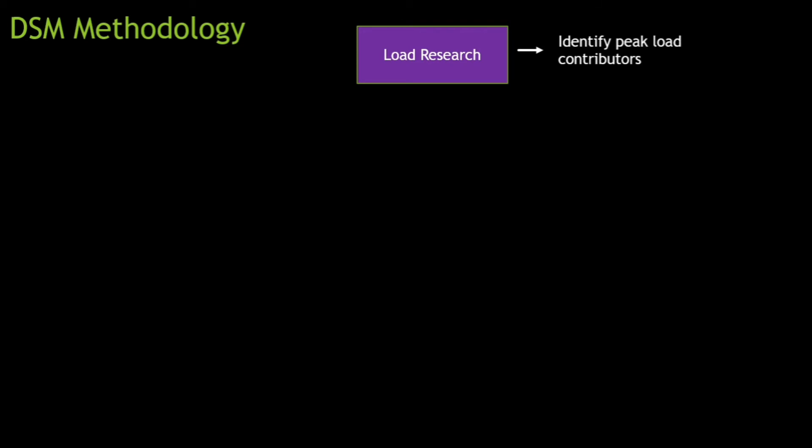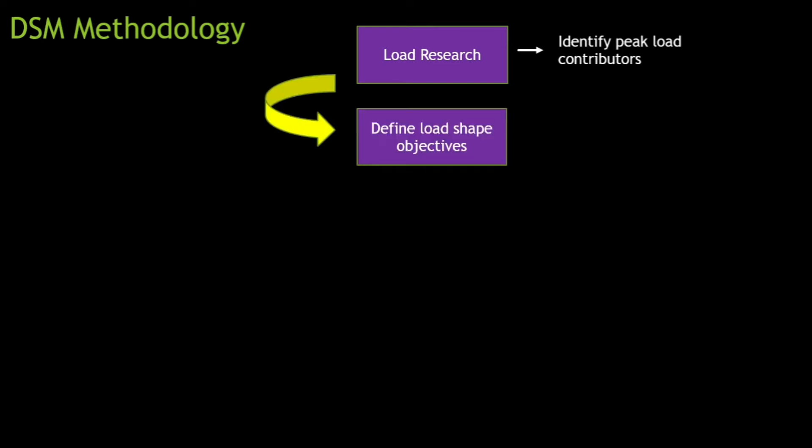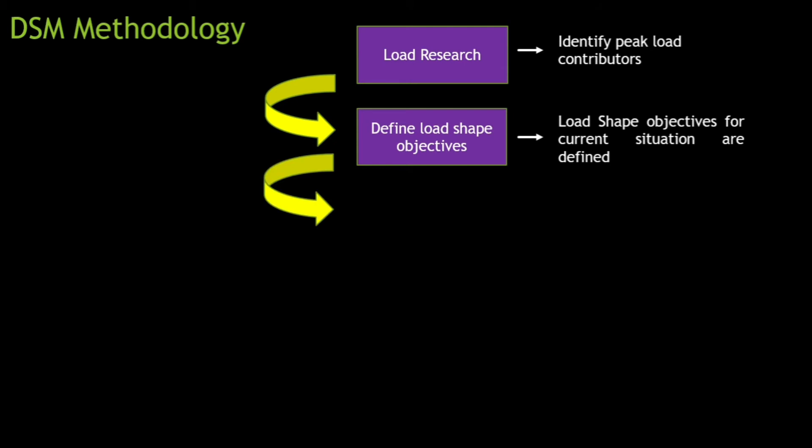Now, what is the methodology? The first step is load research — you have to survey your load. In load research, you identify the peak load contributors. Analyze your plant or industry thoroughly to find out which equipment is responsible for peak load. Until we analyze, we cannot create a plan of action. After load research, the second step is to define load shape objectives. Once you know who the peak load contributors are and at what point in time the peak load occurs, you can define load shape objectives for the current situation.